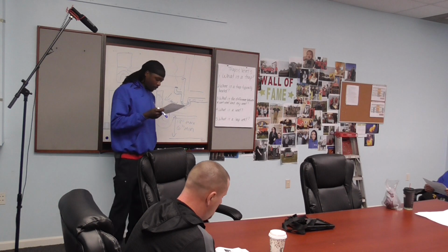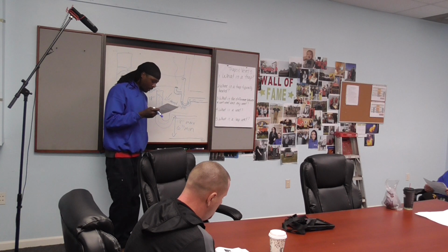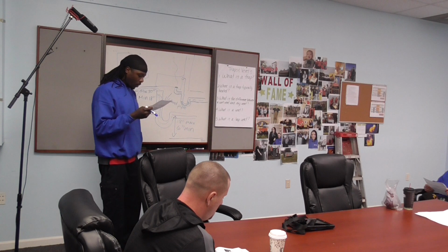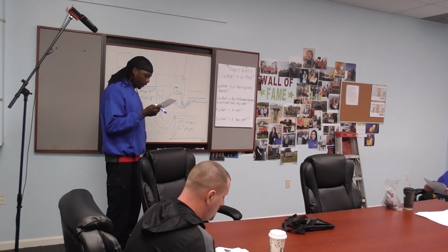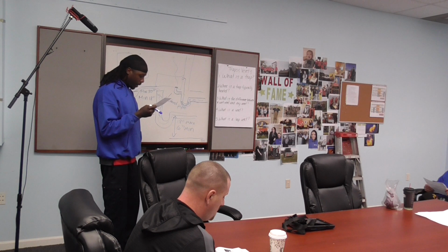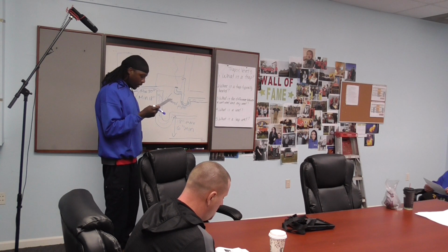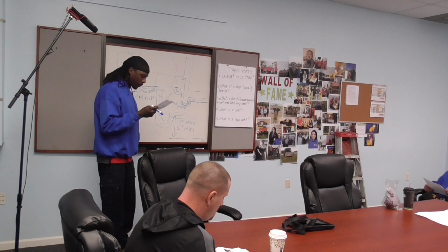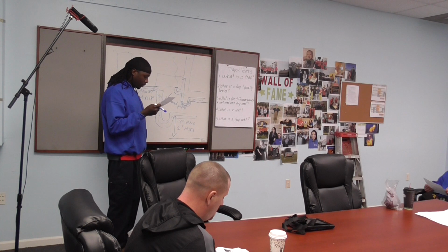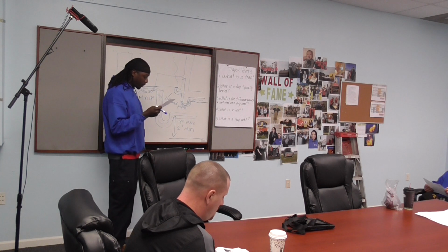Maintaining the water seal is critical to trap operation. Traps might dry out, and poor venting can suction or blow water out of the trap. This is usually avoided by venting the drain pipe downstream of the trap, vented to the atmosphere outside the building. The drain lines never operate at a pressure much higher or lower than atmospheric pressure. Plumbing codes usually provide strict limitations on how far a trap may be located from the nearest vent stack.